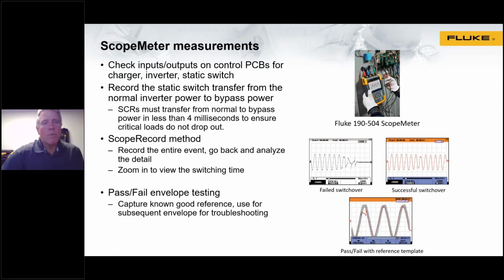We're going to focus a little bit more on some of the same types of measurements, but maybe rather than using a full three-phase analyzer, which you could use, we also have troubleshooting tools, portable tools such as a scope meter, which is a combination of an oscilloscope as well as a meter for meter readings. And it's a great portable tool, anywhere from either 2 or 4 inputs, with a variety of bandwidths. So we have a 500 megahertz product, high bandwidth to be able to capture very short rise time events, namely the Fluke 190-504 4-channel scope meter.